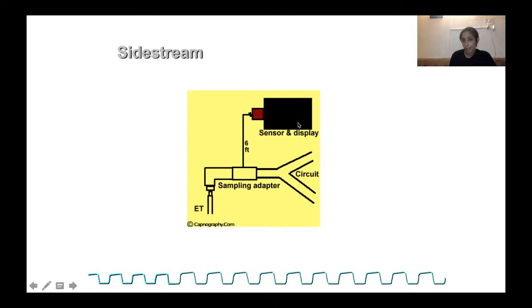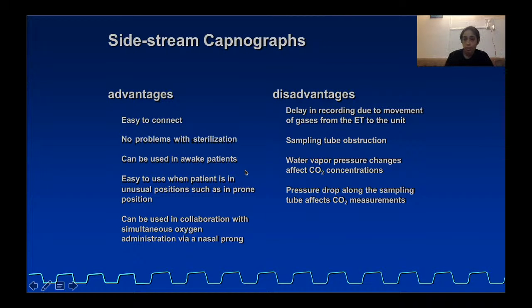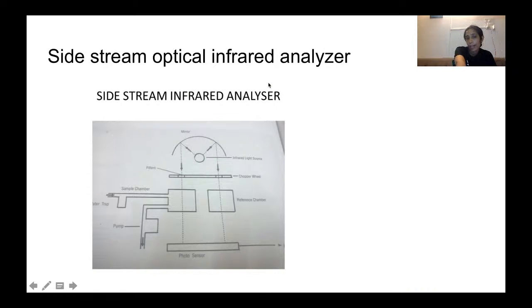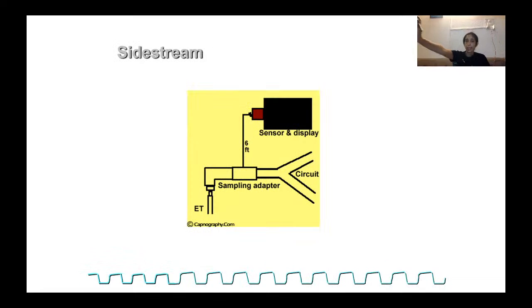So this is your side stream. This is your sensor and display. This is your circuit, where the sampling adapter is. This is your ET tube coming from the patient. So, sorry, it is side stream, right? I told you all it is side stream. From here the gas will enter like this. The sample will be taken here, 6 feet away. This is your sensor and display, and inside the sensor there are two chambers, reference chamber and sample chamber, as we just discussed, and this is your display.